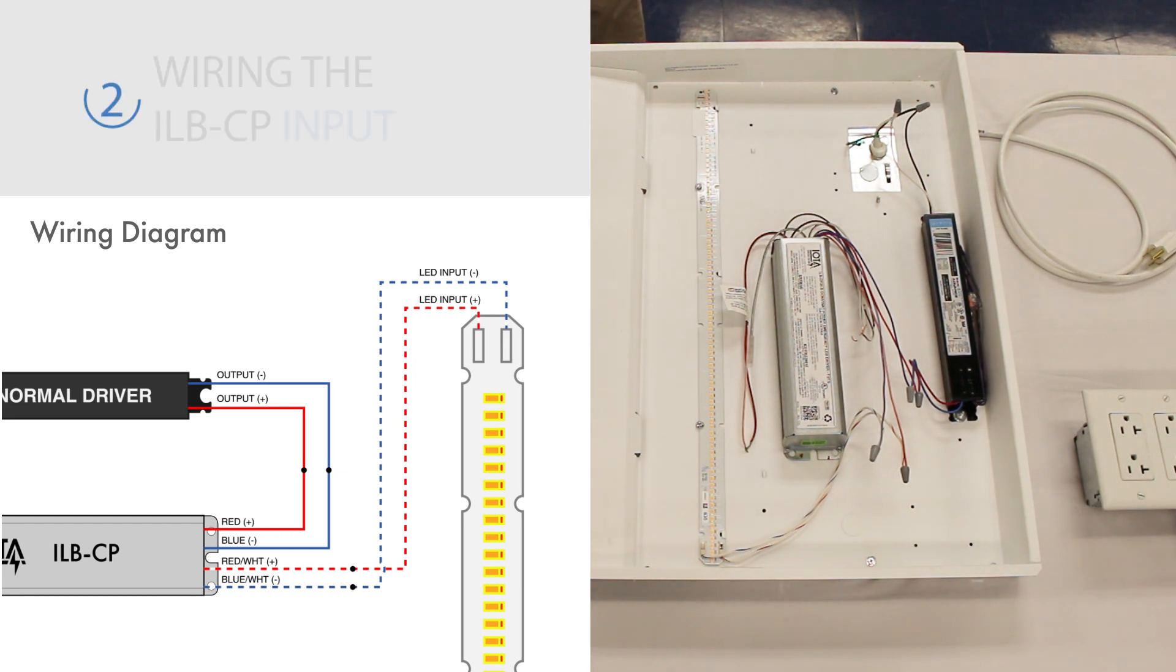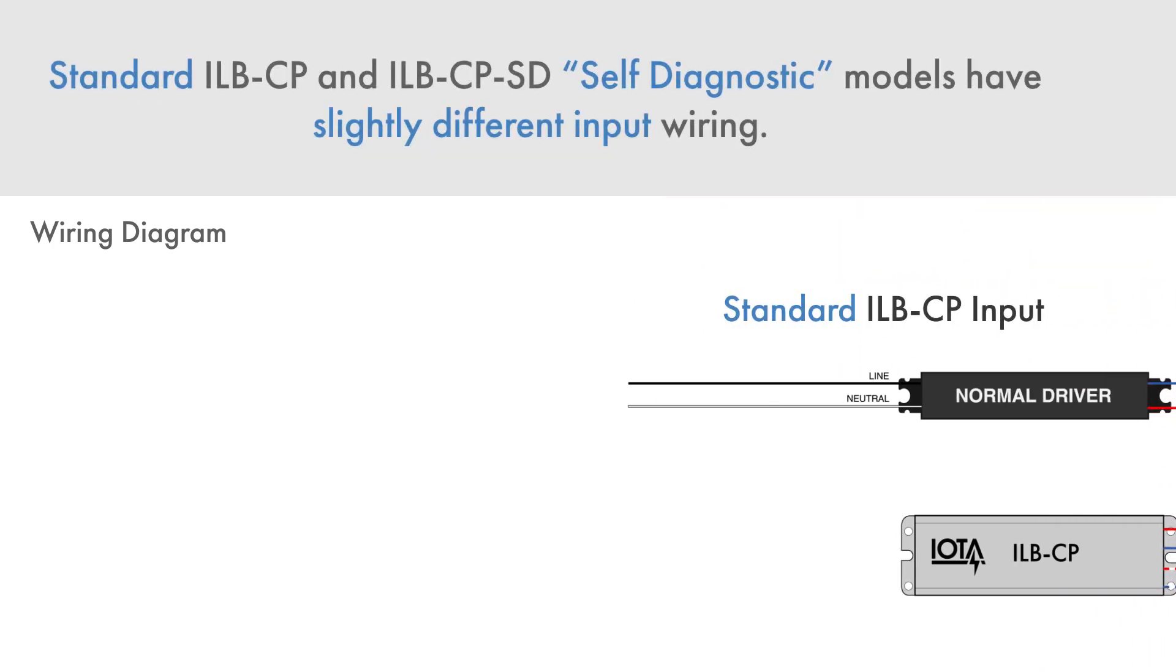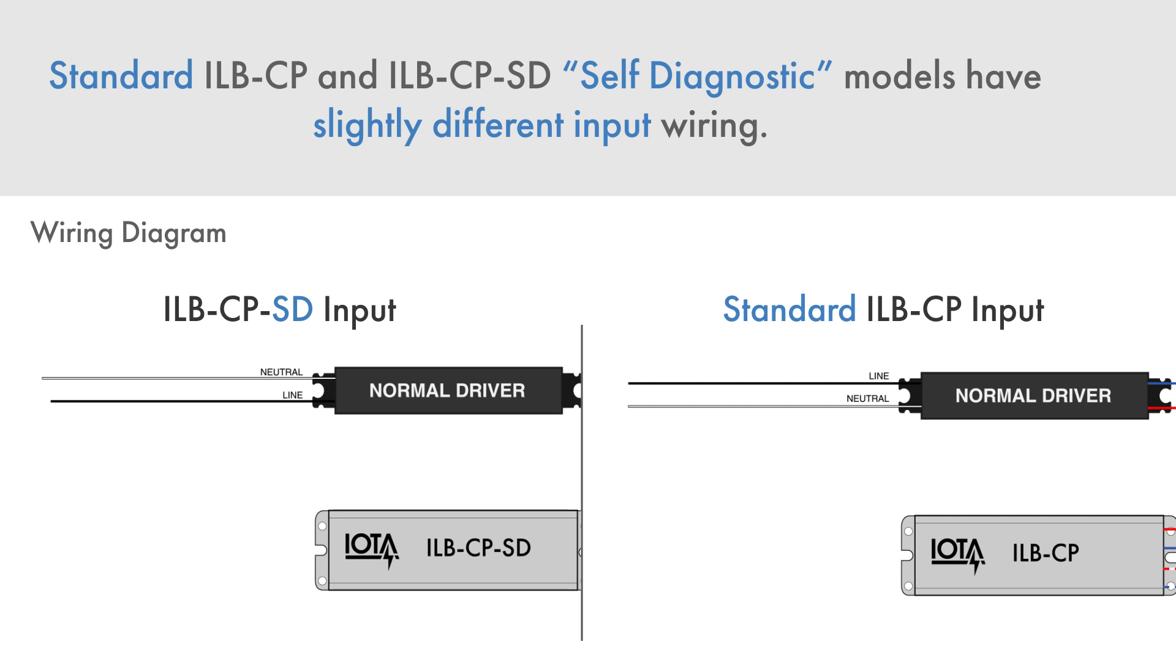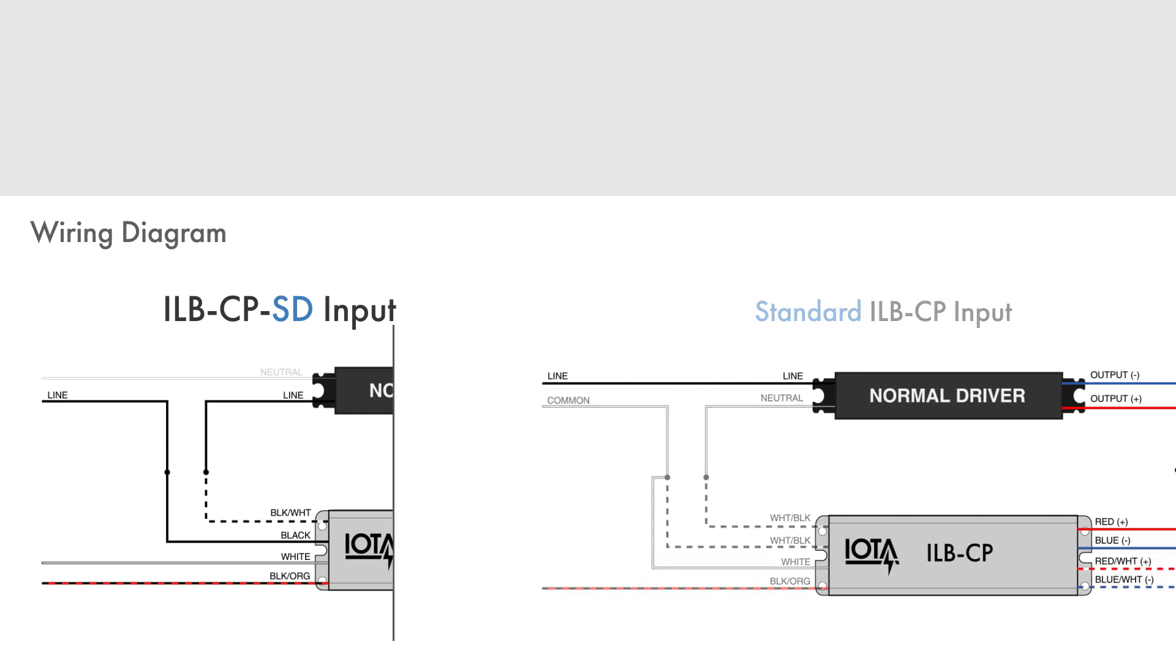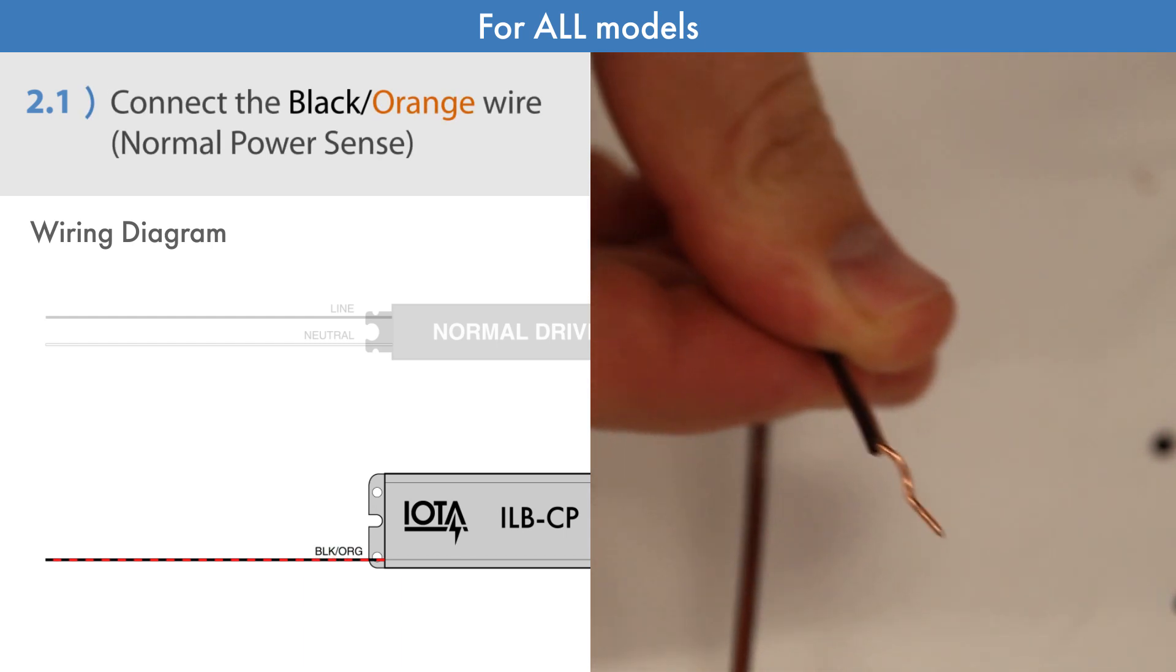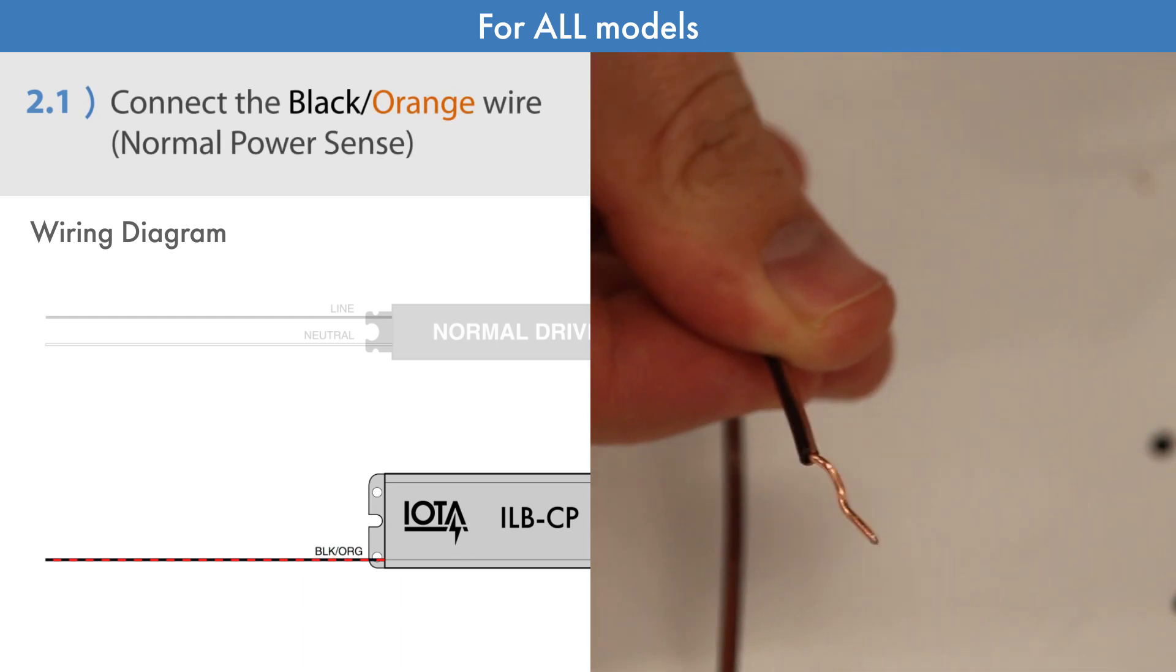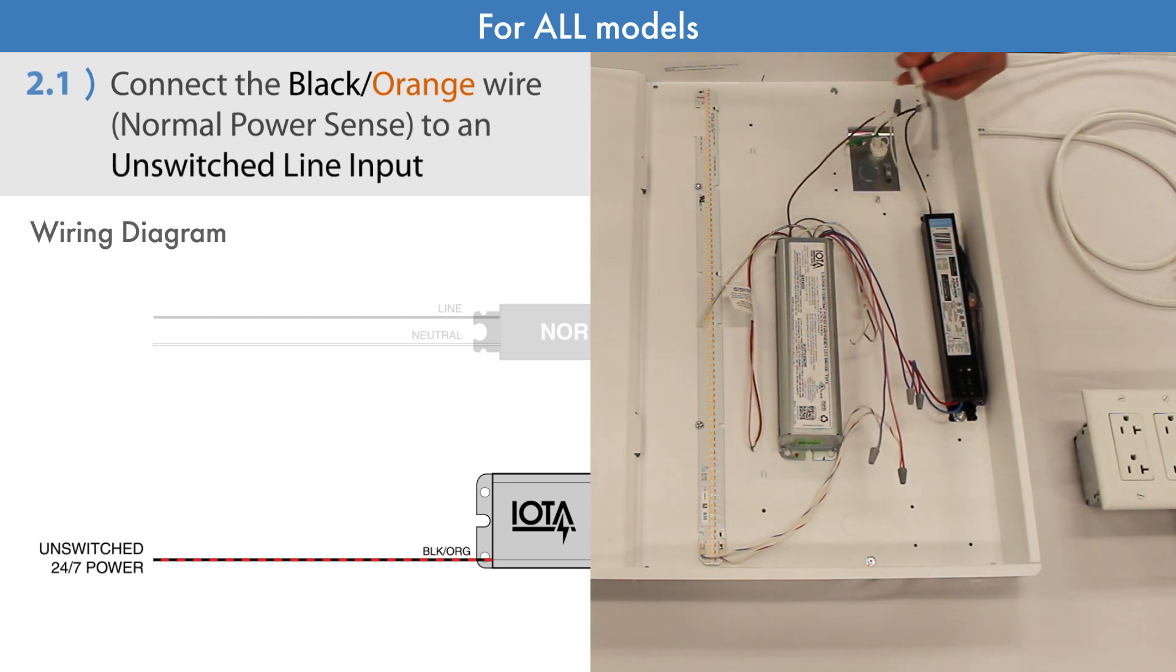We can now wire the ILB-CP input. Note, standard ILB-CP and ILB-CP self-diagnostic models have slightly different input wiring. We will address both here. First, for both models, we will address the black-orange wire which is the ILB-CP's normal power sense and battery charging input. This wire is used by the ILB-CP to both charge its internal batteries and detect whether normal power is supplying the fixture. Therefore, it needs to be connected to an unswitched line input.